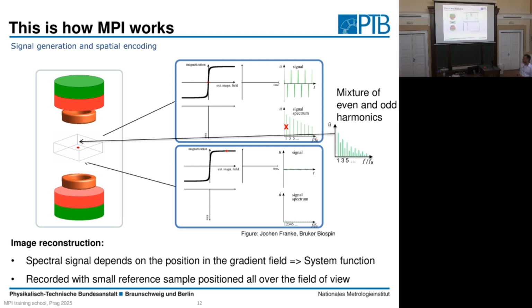They are excited with a sine signal, which has a pure sine form, no harmonics, because the higher harmonics are generated by the nonlinear curve of the magnetic nanoparticles. This is our measurement signal. The analysis of MPI is based only on these higher harmonics, and that's the reason why we can cancel out the first harmonic, the excitation. So it's decoupled.